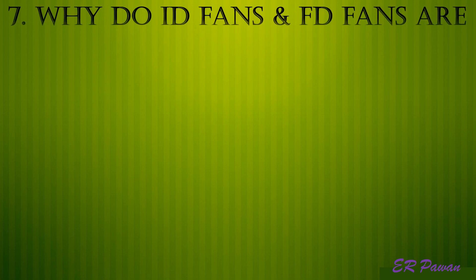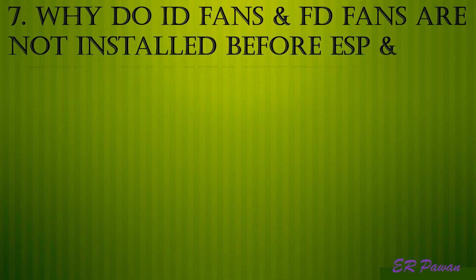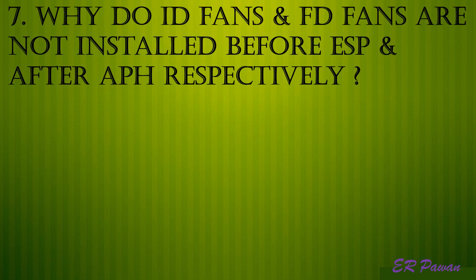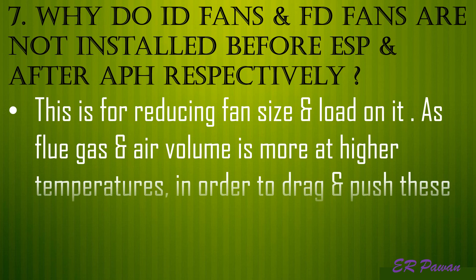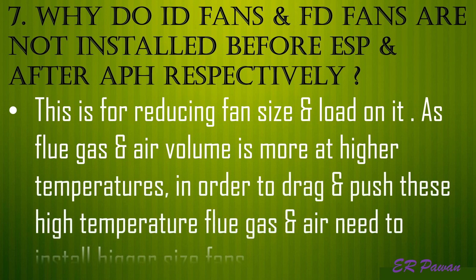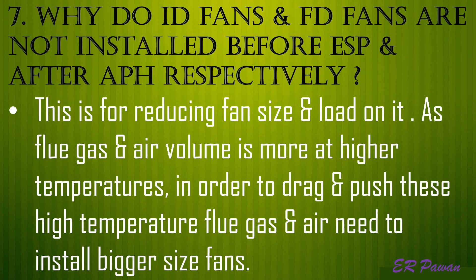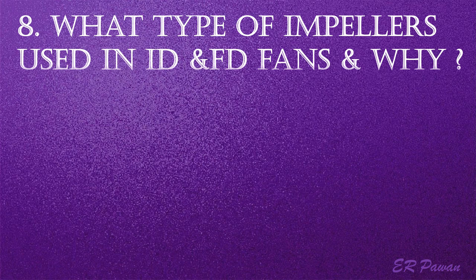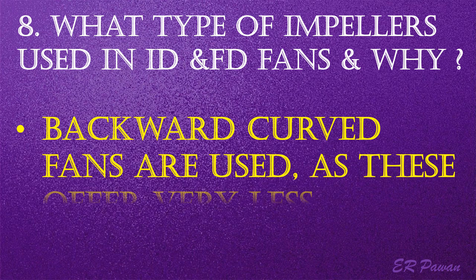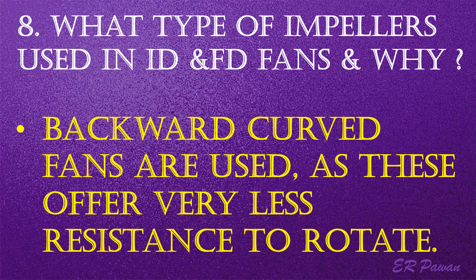Question 7: Why are ID fans and FD fans not installed before ESP and after APH respectively? This is for reducing fan size and load on them. As flue gas and air volume is more at higher temperatures, in order to drag and push high temperature flue gas and air, it would require bigger size fans. Question 8: What type of impellers are used in ID and FD fans, and why? Backward curved fans are used, as these offer very less resistance to rotate.